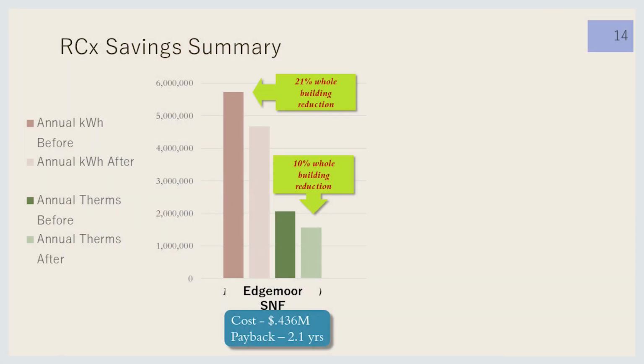This project saved about 21% of whole building electricity use. The measures we implemented included ventilation reduction, demand control ventilation, and a few other things. We weren't attacking the whole building, just some subsystems that showed a lot of promise for opportunities to reduce, but those measures ended up saving over 20% of the whole building energy use. That includes everything: all the equipment, lighting, televisions, phone charging, whatever. The gas savings were 10%. The cost was under $500,000, paid back in 2.1 years.